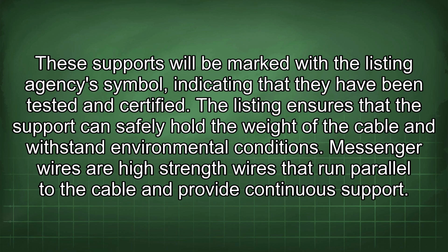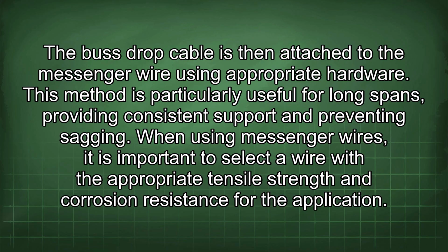Messenger wires are high-strength wires that run parallel to the cable and provide continuous support. The bus drop cable is then attached to the messenger wire using appropriate hardware. This method is particularly useful for long spans, providing consistent support and preventing sagging. When using messenger wires, it is important to select a wire with the appropriate tensile strength and corrosion resistance for the application.